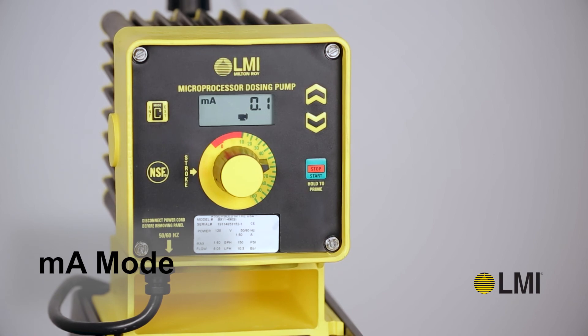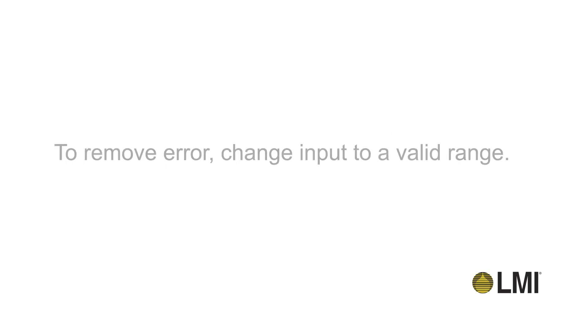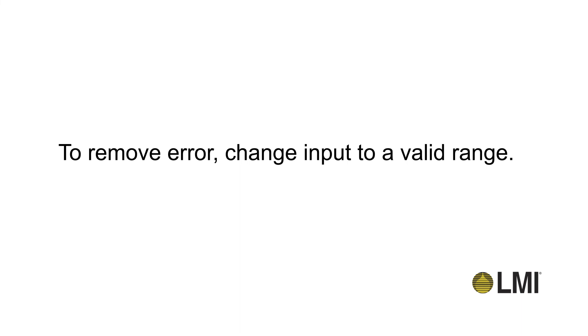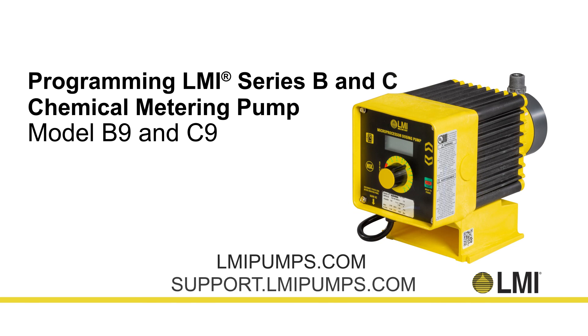The value input range is from 0.5 to 21 milliamps. An E5 error code will be displayed intermittently if the selected range is below 0.5 milliamps or above 21 milliamps. To remove the error, change the input to a valid range. Visit LMIPumps.com and support.LMIPumps.com for more product information.